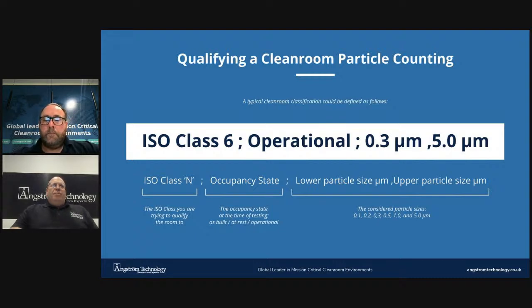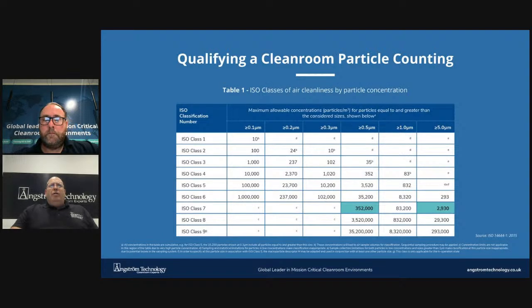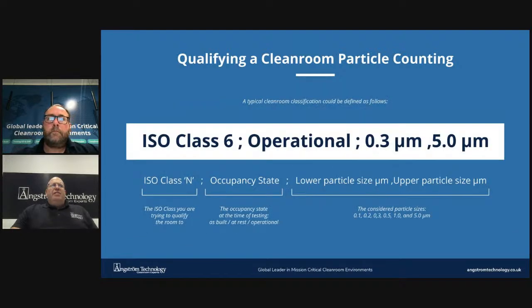The lower and upper considered particle sizes, from table 1 above, you can see that the particle size is usually considered as 0.1, 0.2, 0.3, 0.5, 1 and 5 microns, with the most popular being the 0.3, 0.5 and 5 micron sizes. So a typical clean room classification, as shown on the screen, could be stated as ISO class 6, operational, 0.3 microns, 5 microns.